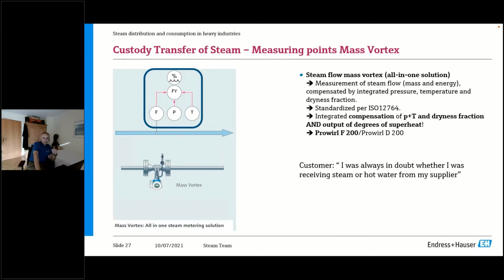Because if you measure 180 degrees C and 10 bar, for instance, you think, okay, that's saturated steam. I hope I have 100% dry steam. But in case that is only 90% dryness fraction, same pressure and temperature, you would get overcharged by 10%, so to speak, because you are paying for all the warm water you're getting as well. And only that vortex meter can actually tell you, with that dryness fraction, what am I really getting? What is really in that pipeline?